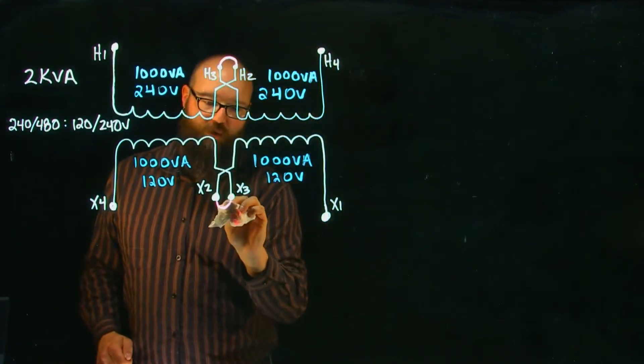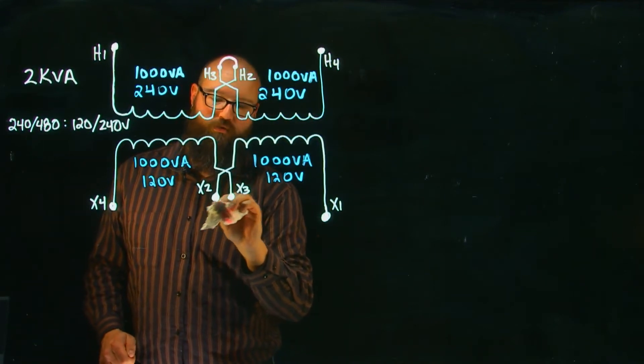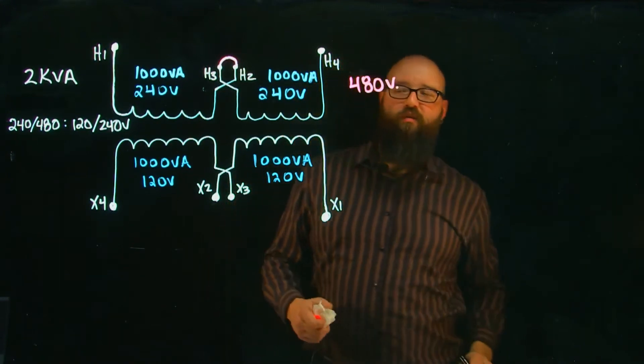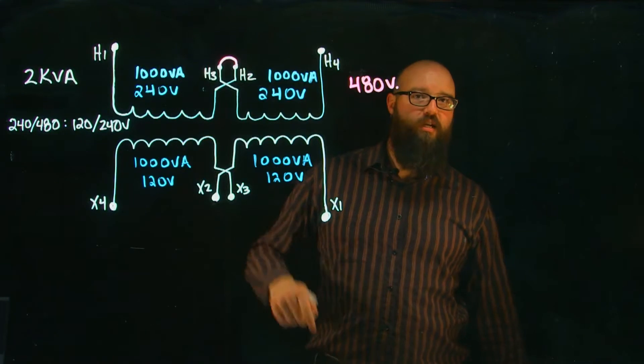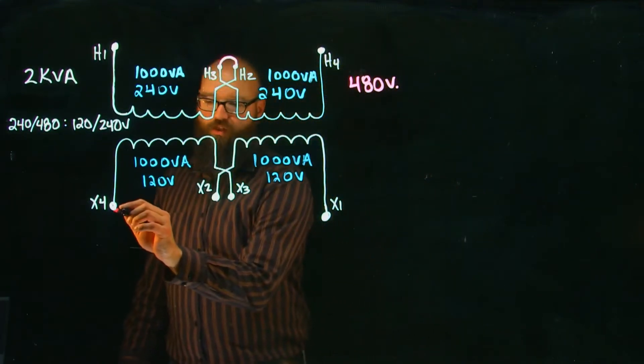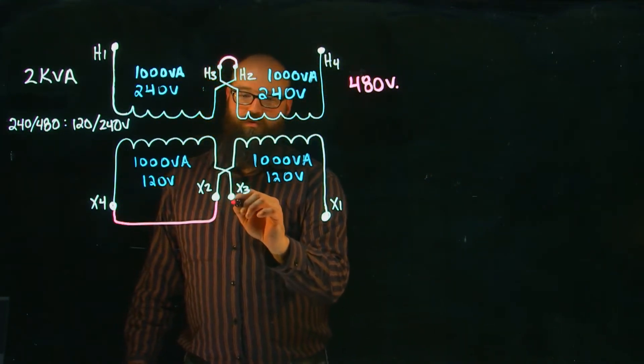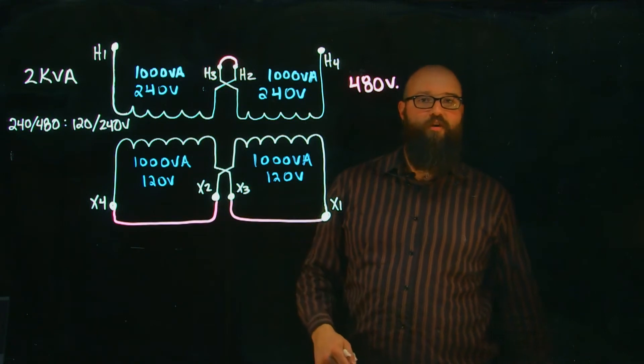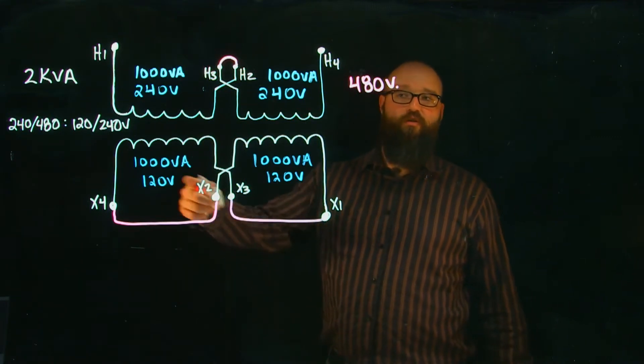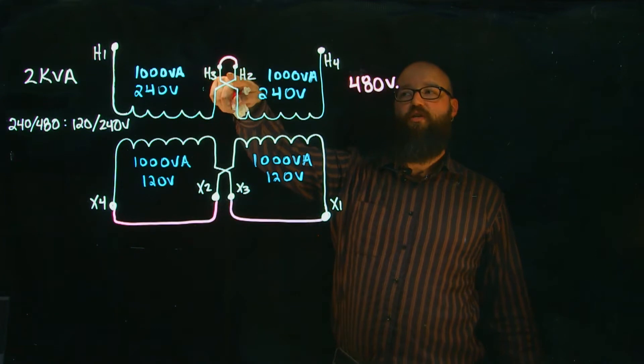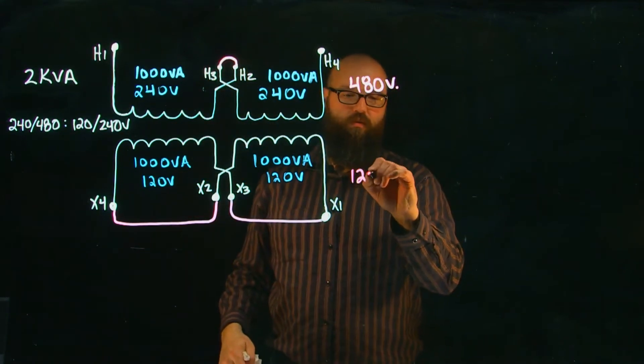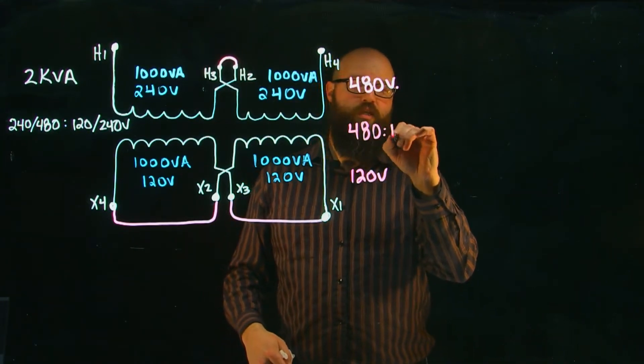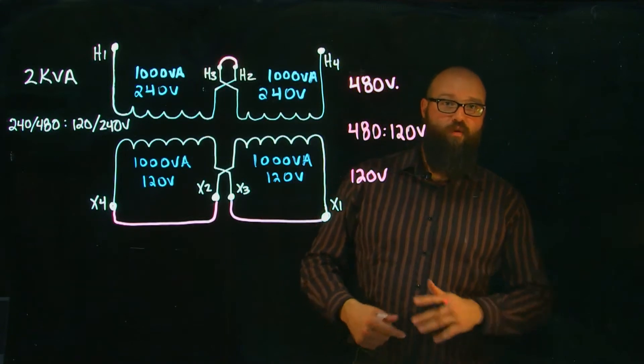Now we'll remove the series jumper on the secondary but leave the series jumper on the primary, so we still have 480 volts — 240 plus 240. On the secondary side we're going to parallel the coils instead. When two equal voltages are paralleled, the output voltage remains the same, so we get 480 input and 120 output — a 480 step-down to 120 volt transformer.